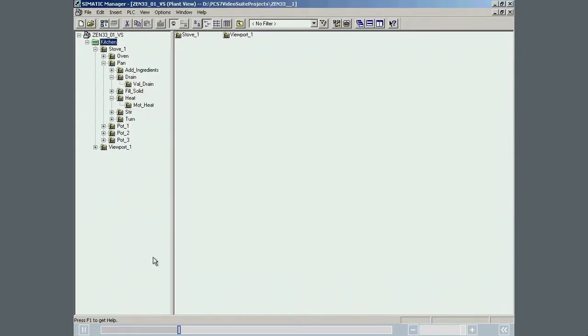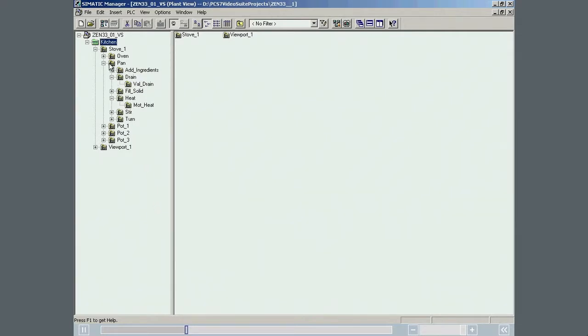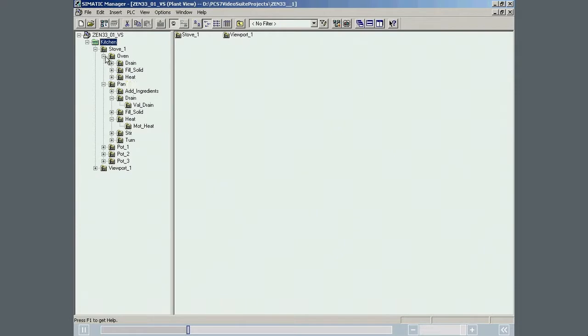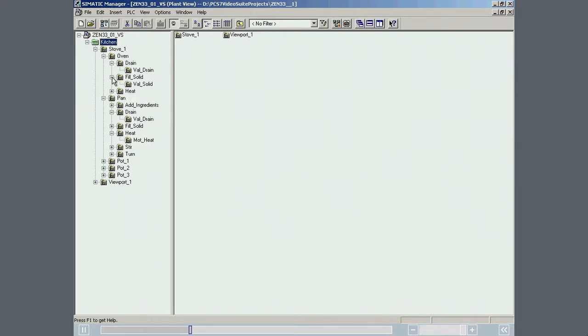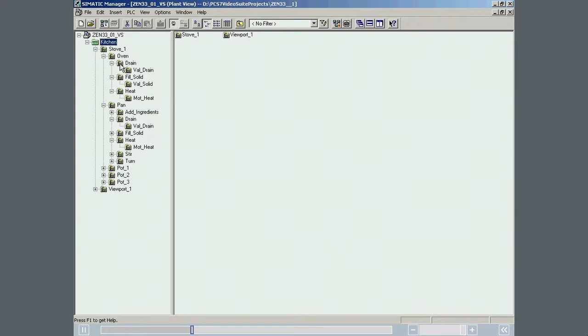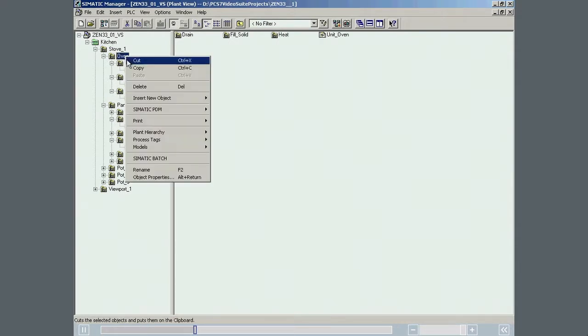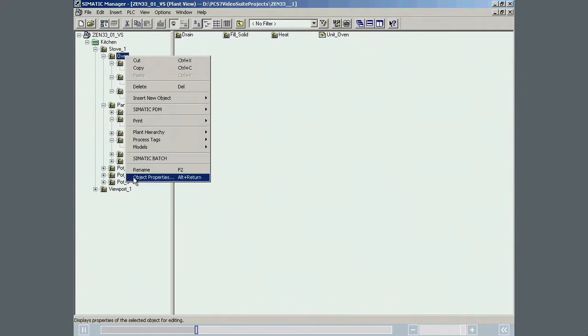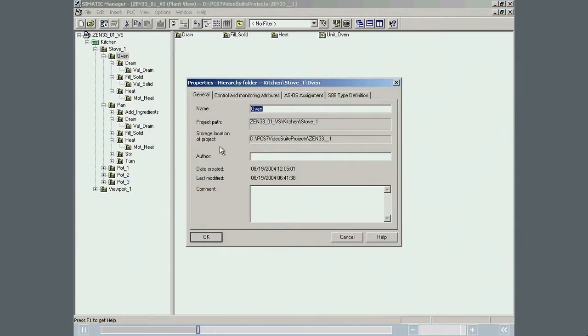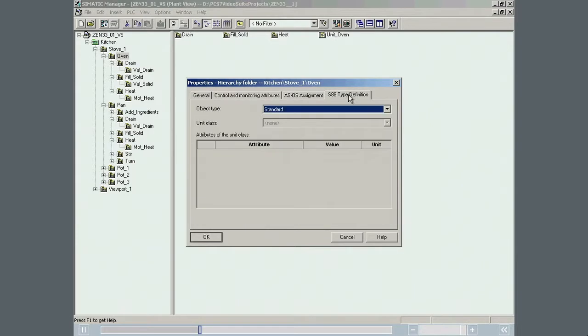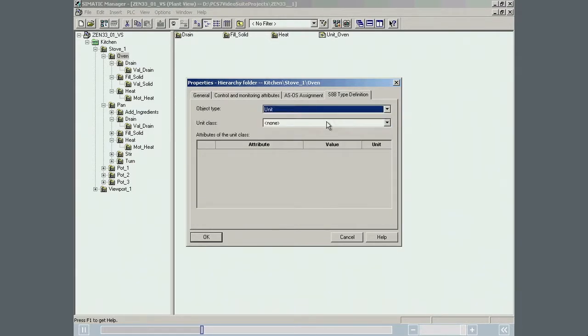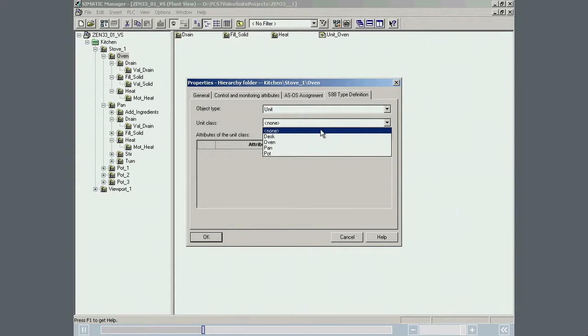In the next step, the units and equipment modules are assigned to Simatic Batch. This is done in the Properties dialog of the relevant folders in the plant hierarchy. We would like to show you a classification based on the example of the Oven unit and its Drain equipment module. The Properties dialog of the Oven folder is opened and the object type of unit is set. The unit type is now Oven.